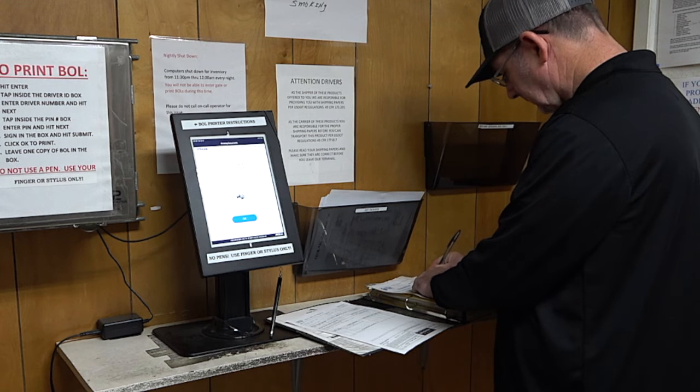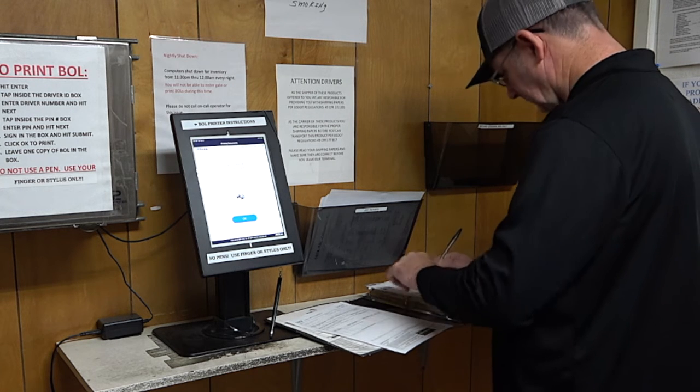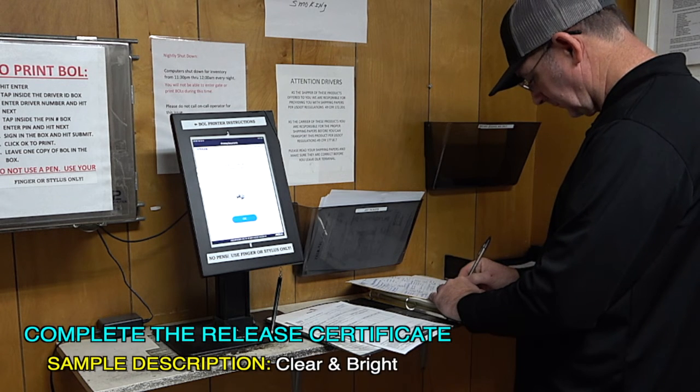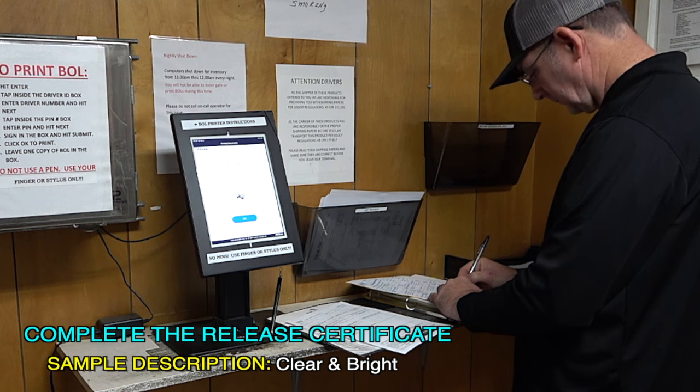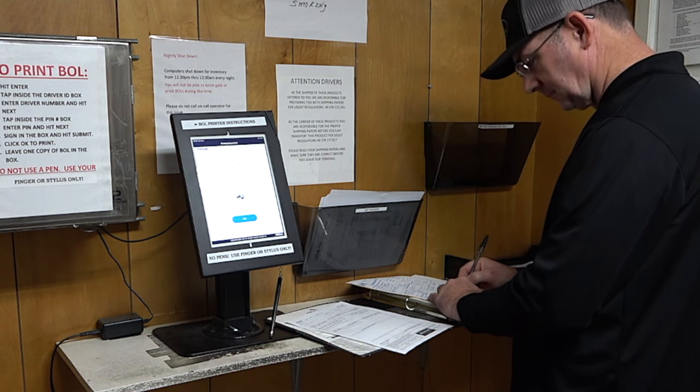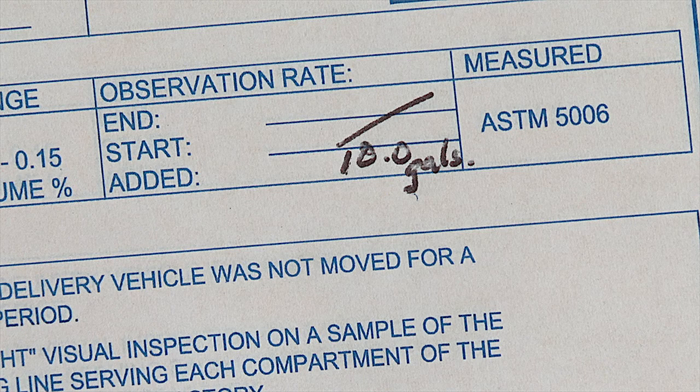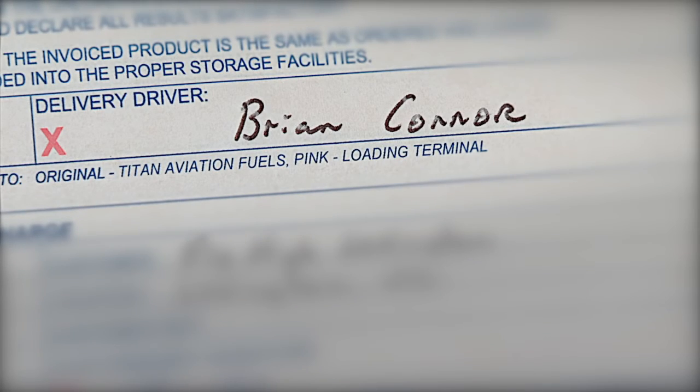The transport driver completes the release certificate by recording the results of the post-load inspection. This should include a clear and bright sample description and the fuel API gravity. If Avgas was loaded, the color of the product should be recorded. If Jet A with FSII was loaded, the color of the product, FSII meter readings, and the total amount of FSII injected should be recorded. Finally, the transport driver signs the certificate. If the release certificate is not filled out properly, the airport may reject the load.